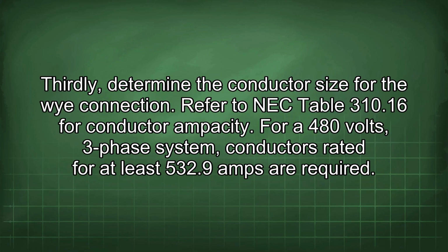Thirdly, determine the conductor size for the Y connection. Refer to NEC Table 310.16 for conductor ampacity. For a 480 volts, 3-phase system, conductors rated for at least 532.9 amps are required.